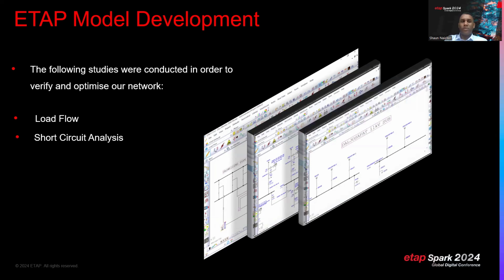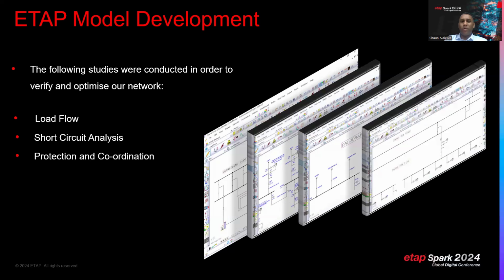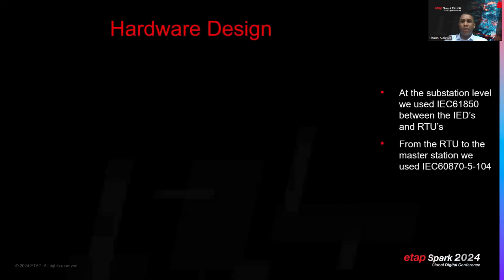The second step was to perform short circuit analysis to determine the fault level calculations and to see whether they were within the ratings of the switchgear that's been installed in our network. The third part was to do the protection and relay coordination of our network to ensure that the system operates the way it should and there is no miscoordination in event of a fault that may occur. Once this was done, we then moved on to the hardware design part.